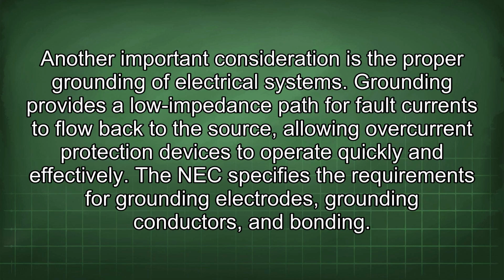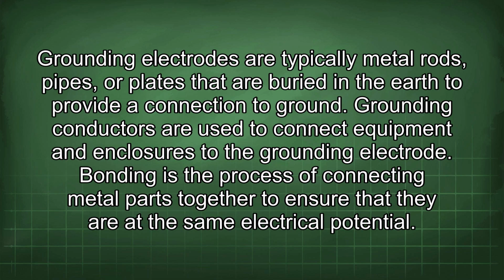Another important consideration is the proper grounding of electrical systems. Grounding provides a low impedance path for fault currents to flow back to the source, allowing overcurrent protection devices to operate quickly and effectively. The NEC specifies the requirements for grounding electrodes, grounding conductors, and bonding. Grounding electrodes are typically metal rods, pipes, or plates that are buried in the earth to provide a connection to ground.